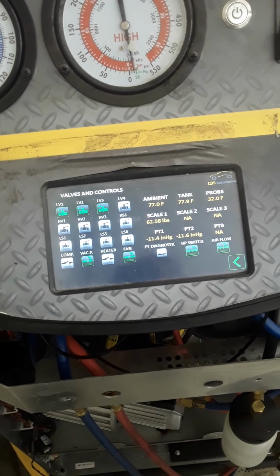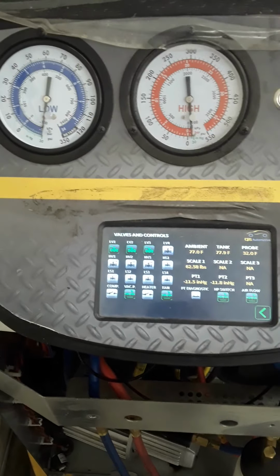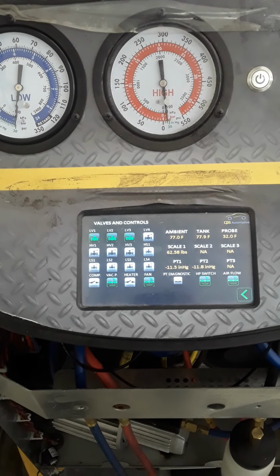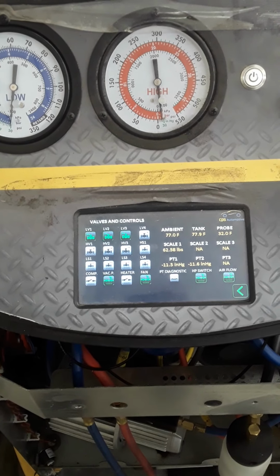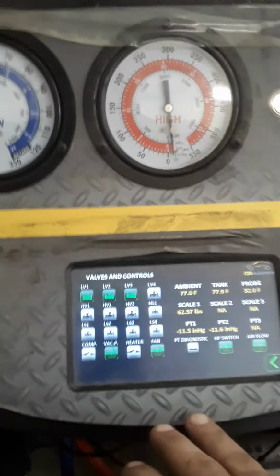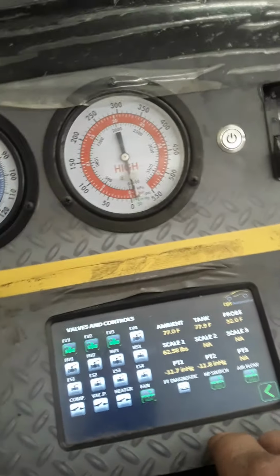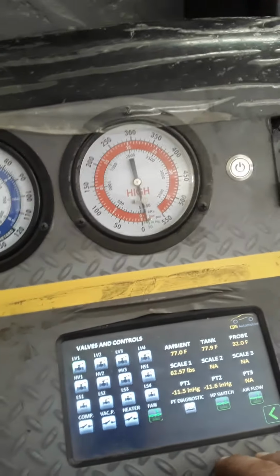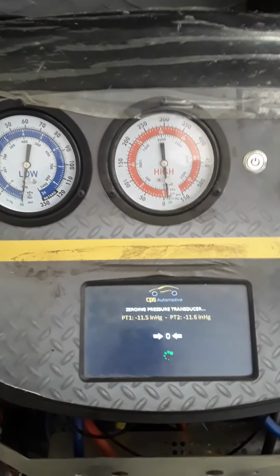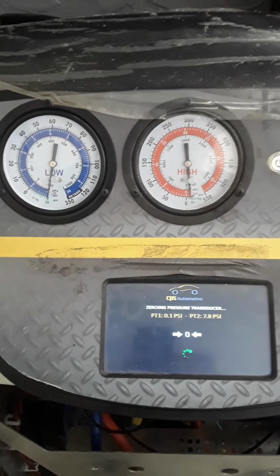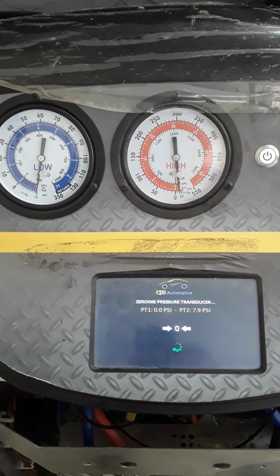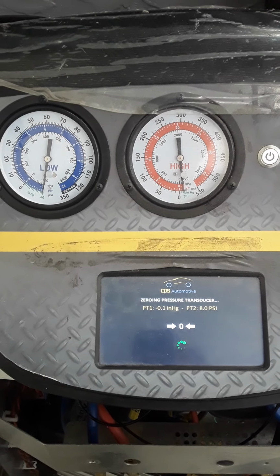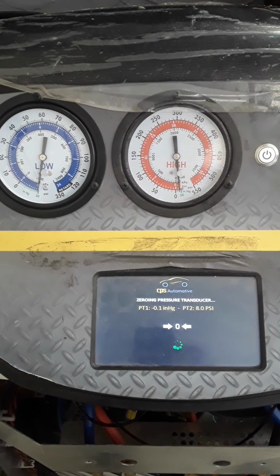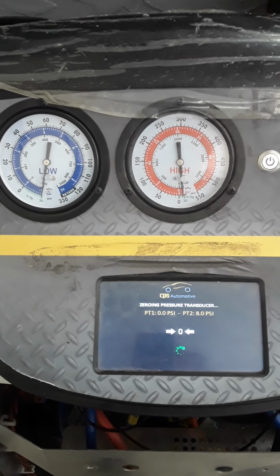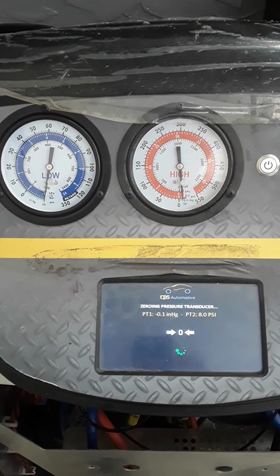And I remember you telling me about that. Yep, and what he's telling me will cause the same thing. Now, if he was anything besides right dead on 1 PSI, I would say something else. But what he's telling me, 0.7, I guarantee you that brass cylinder, that little eye is clogged. That's on the pressure transducer on PT1. He's got to take the pressure transducer out, reach down there, pull that brass cylinder out, replace it, put it back in, and then calibrate it, and I guarantee it'll work.